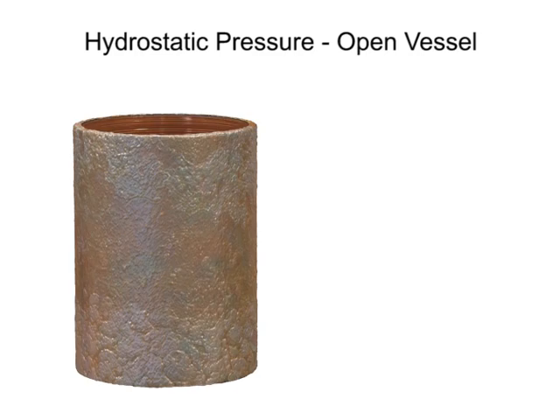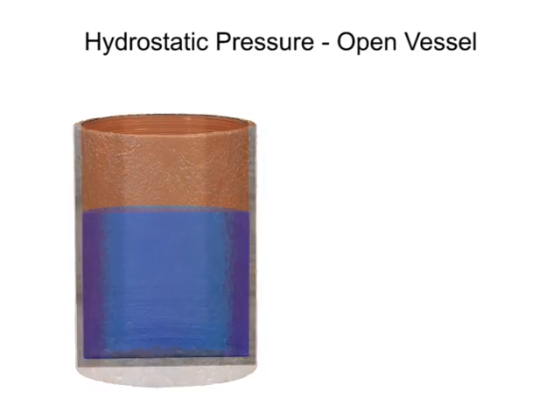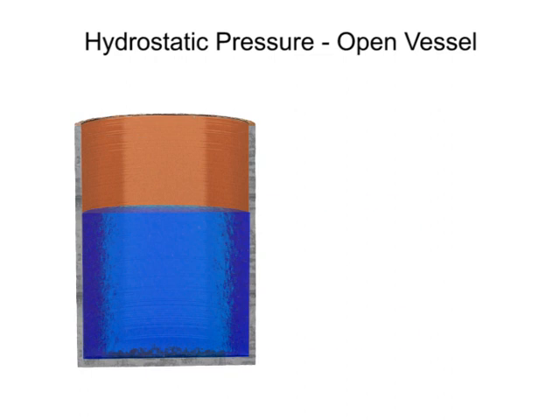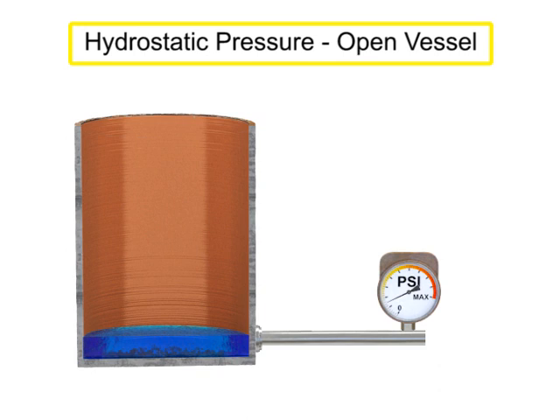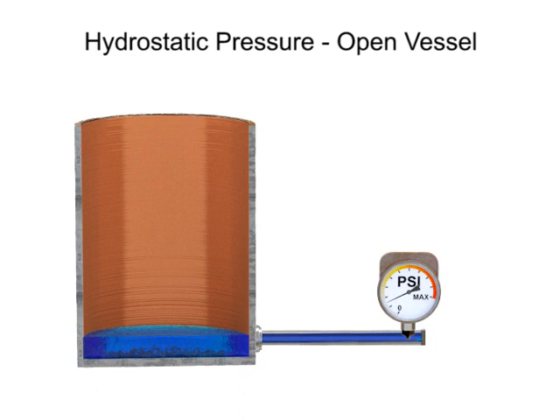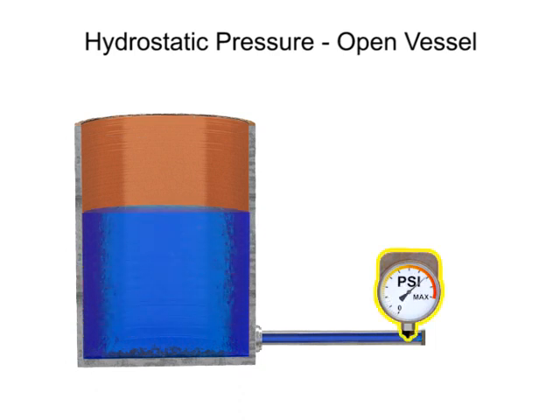The pressure exerted by a fluid material in a vessel is directly proportional to its height multiplied by its density. Hydrostatic pressure, or head pressure, is the force produced by a column of material. As the height of the material changes, there is a proportional change in pressure.